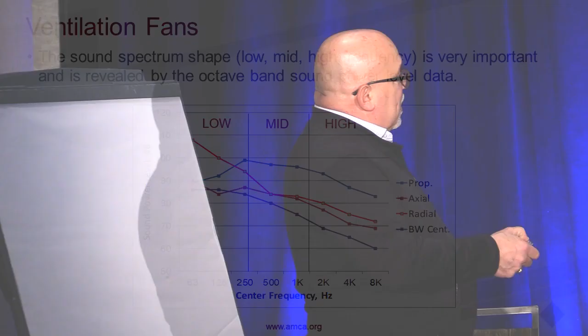A lot of times you'll get a call and they say, hey, we're running at 100 dBA, we've got a centrifugal fan. Well, not a centrifugal fan. We have a noise source, we don't know what it is, but we're running 100 dBA. Well, you need to have the octave band data, because if you look here, by definition, when you run the calcs, both of these curves run at 100 dBA, but they would both have two different noise control solutions.